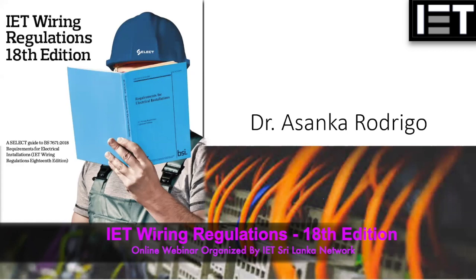Yeah, but doctor, I have noticed only two cables coming from the driver to the lighting fitting, like a plastic fitting. As I said, if it is plastic and you do not have any metal enclosure or anything, then there is no way to connect the earthing connection. So in that case, you don't need it.